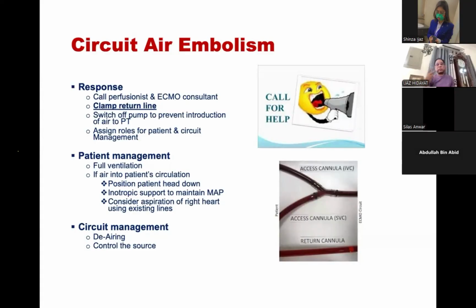So clamp the return, not the access. If you clamp the access line, you will not be able to suck, and it will create more air in the circuit. So clamp the return and not the access line. Put your Luer lock syringe on the pre-membrane pigtail, not on the post-membrane pigtail, because you want to de-air.